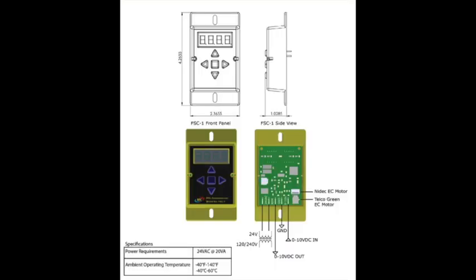Looking at the back of the controller, you can see that there are input terminals for 24 volts AC to power the controller, a 0 to 10 volt DC output terminal, a ground terminal, and a 0 to 10 volt DC input terminal.